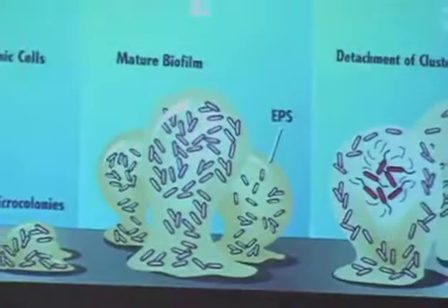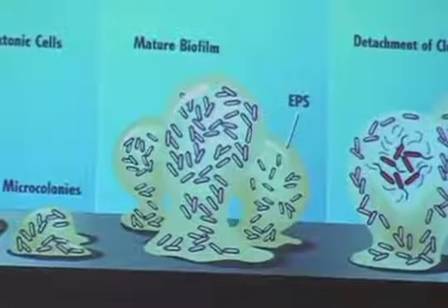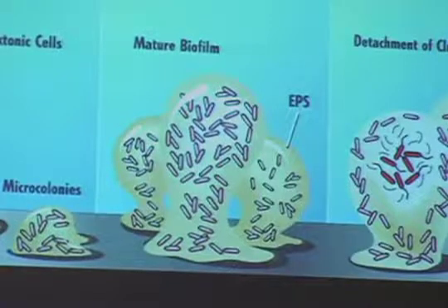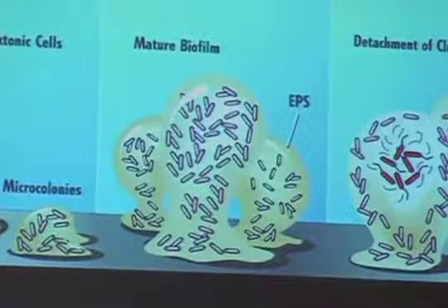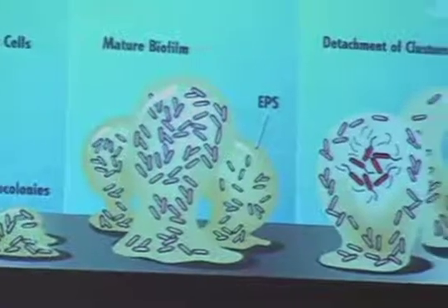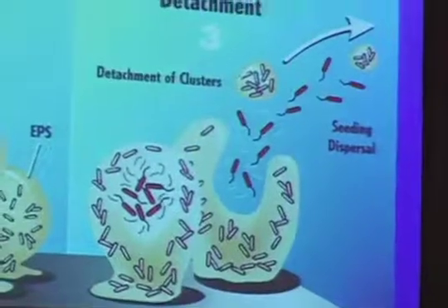It actually digs down into the metal surface and causes some very damaging pitting corrosion. This biofilm, because it grows at certain points and grows to certain levels and heights, because of the flow, actually discharges and leaks itself back out into the system. It goes around the tower and it finds a way to establish residence somewhere else.